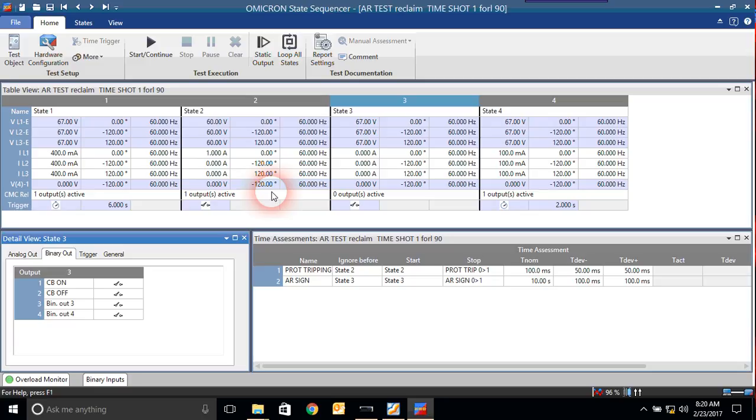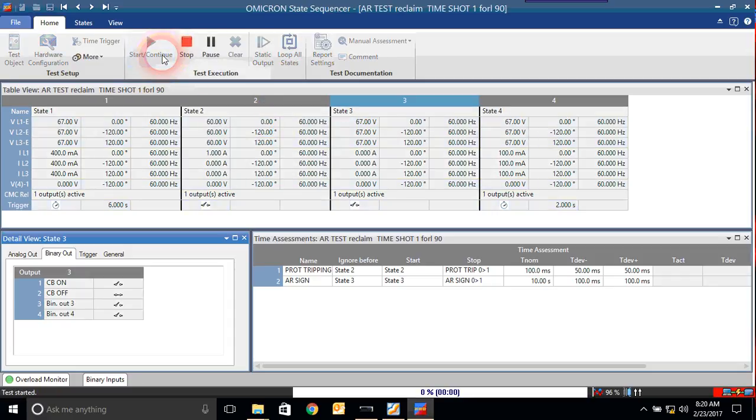After ABB relays, you can work on any relay. Okay, now I will simulate here, no synchro check here. So I will inject, I will normalize here also, CB off. See what will happen. The function should not work.